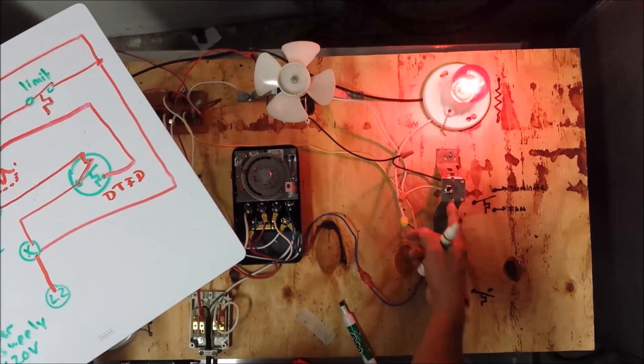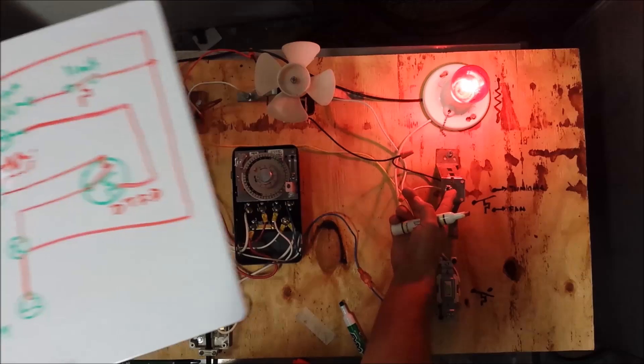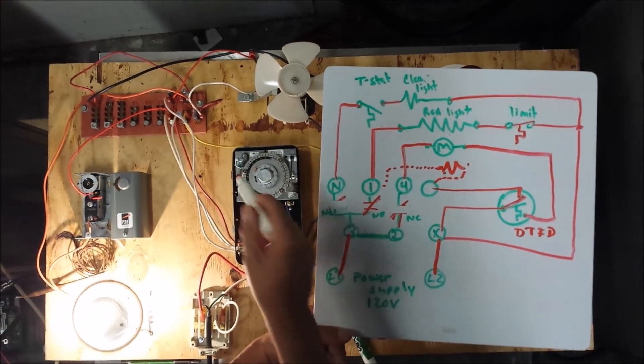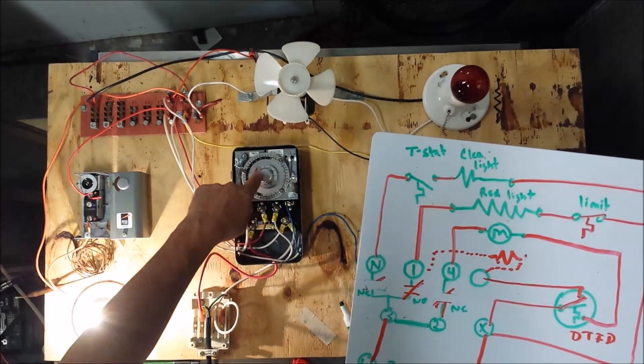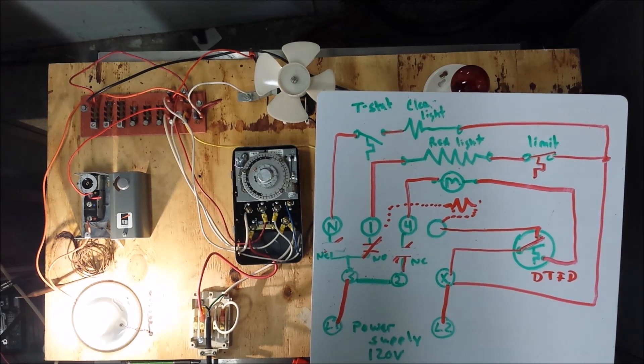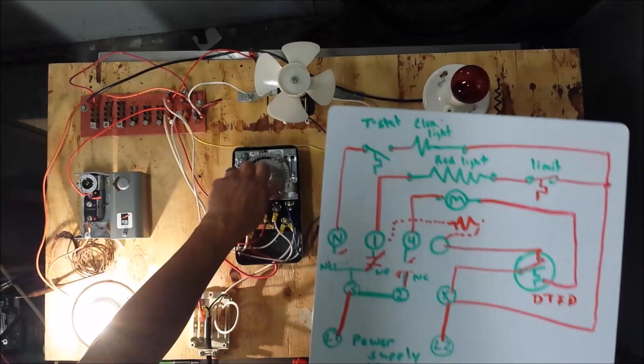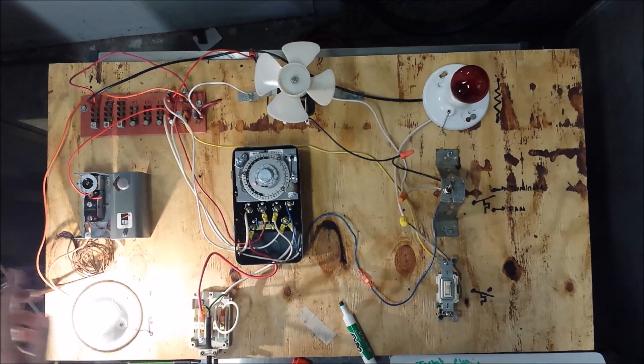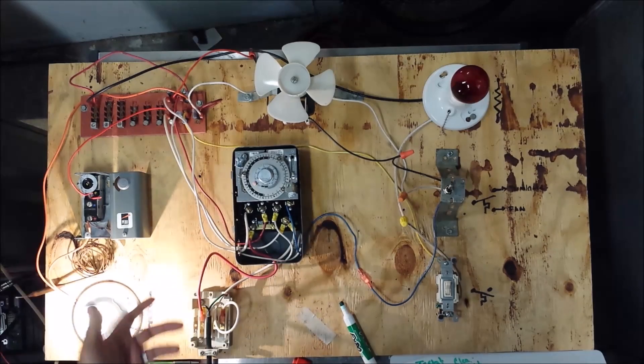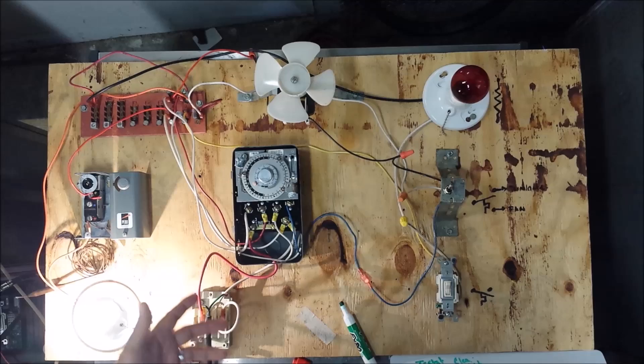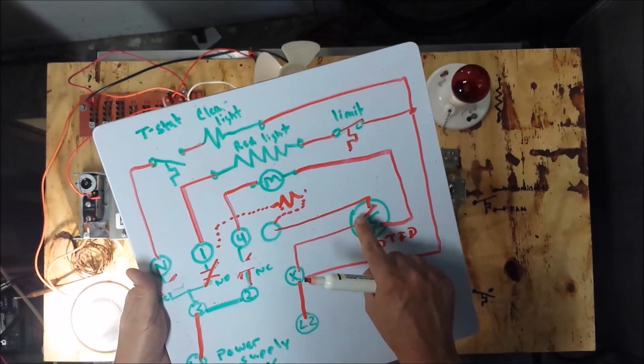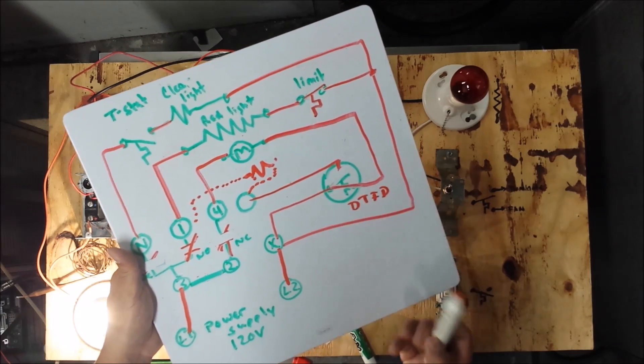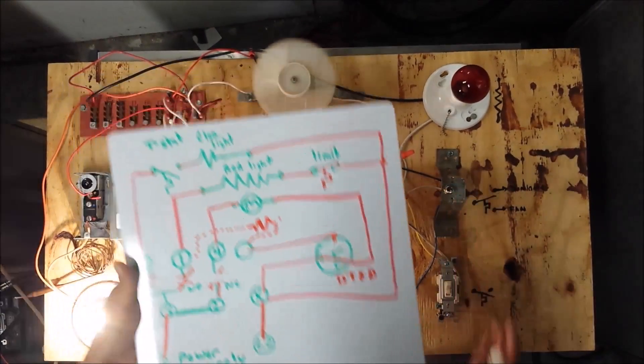Temperature goes up, the thermostat makes the switch, which energized our coil behind the clock, which kicked it out of defrost — even though the clock may still show it's in defrost. Now our light bulb comes back on, representing our coil to our valve. It's energized, refrigerant flow should be flowing, our compressor should be running. The temperature in our evaporator should be dropping, and when that starts to drop, our thermostat located at the evaporator will close this circuit, and on comes the fan.